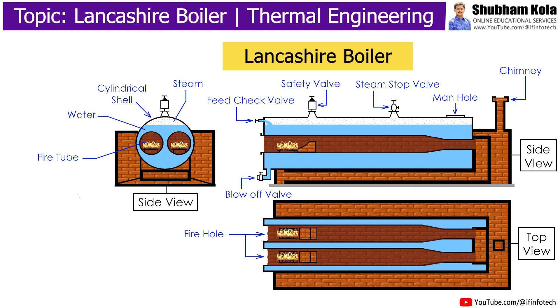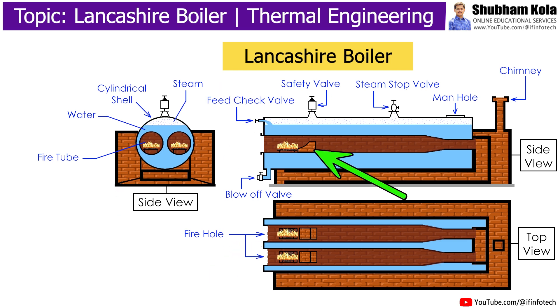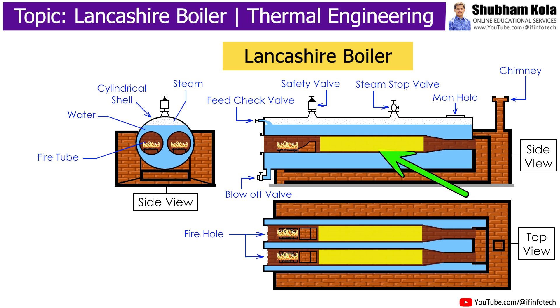During working, water is pumped into the machine through the economizer such that the fire tube is fully immersed in water. The fuel is burned at the grate, where a small arch-shaped brickwork is provided at the end of the grate to deflect flue gases upward and prevent entry of burning coal and ash into the fire tubes.